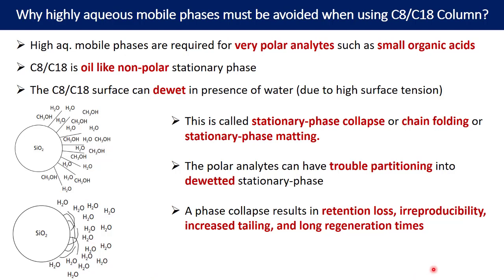The second important issue is irreproducibility in retention time. Since de-wettability is not consistent and can change over time, retention time variation will occur. If you are seeing a lot of retention time variation, it could be due to highly aqueous mobile phases. Additionally, peaks will start tailing due to the high aqueous content, and once analysis is complete, you will need to regenerate the de-wetted stationary phase by passing organic solvent through it — which takes longer than with standard organic-containing mobile phases.